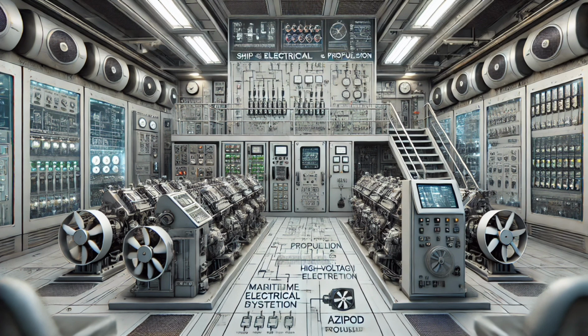And what about materials? Are there specific ones they use for these high voltage transformers? Oh, absolutely. Material selection is super important here. For the high voltage windings, they usually use high purity copper wire, sometimes round, sometimes rectangular, and it's heavily insulated, of course, to prevent those high voltages from leaking out. They'll also use things like glass fiber webbing or special glass mats impregnated with epoxy resin to provide more insulation and support between the layers of the windings. And the core of the transformer, the part that guides the magnetic field, is typically made of laminated silicon steel, all carefully stacked to minimize those energy losses that come from eddy currents and hysteresis.